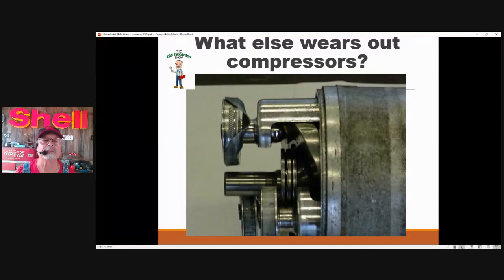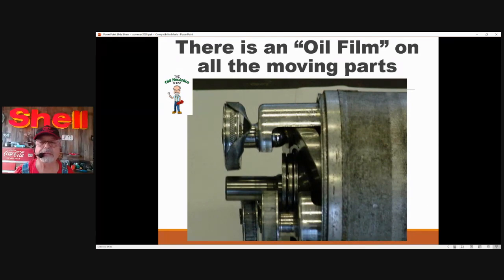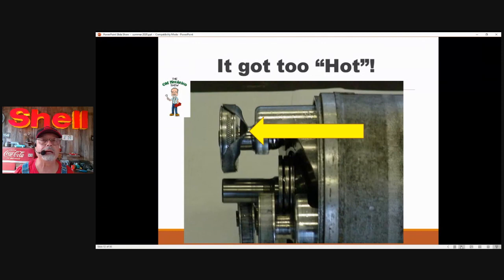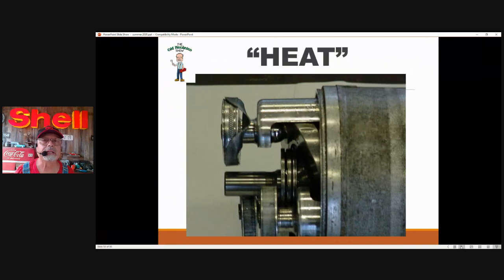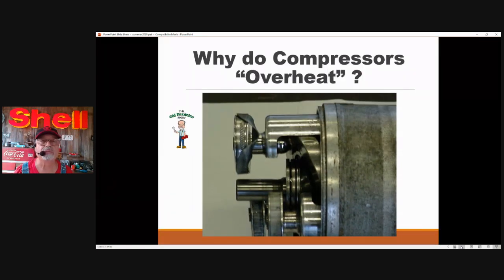What else wears out the compressor? This one does have an oil film on all the moving parts, but why is the Teflon ring out of its groove? Not because it ran out of oil — because it got too hot. This compressor overheated. Compressors get hot like an engine and get damaged. The Teflon ring has decided to leave the groove. Compressors overheat.